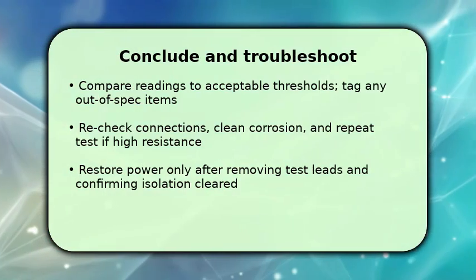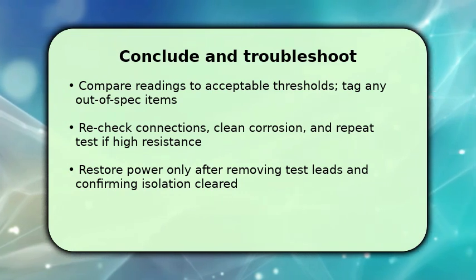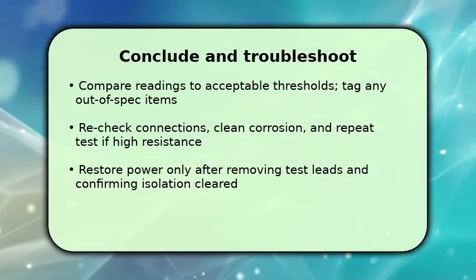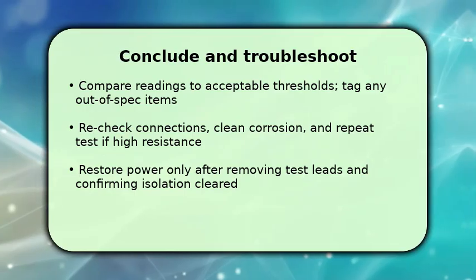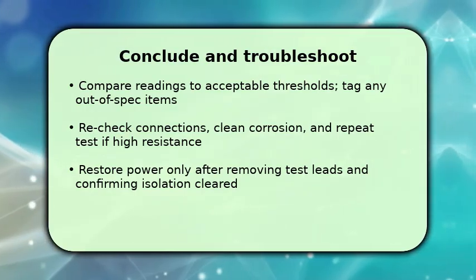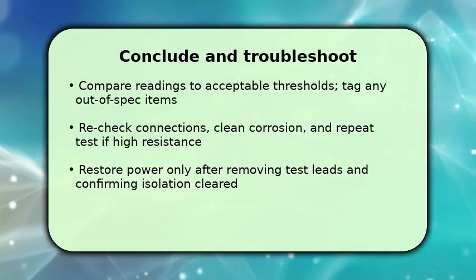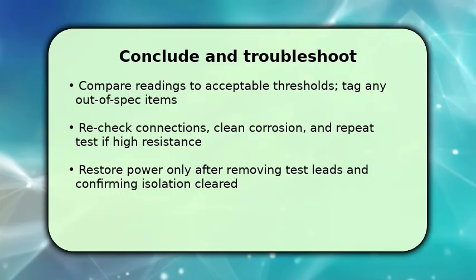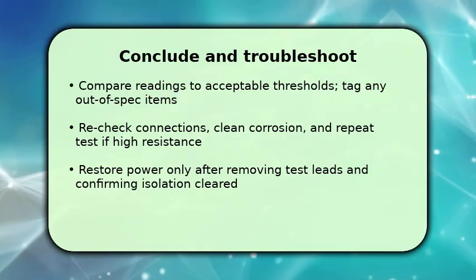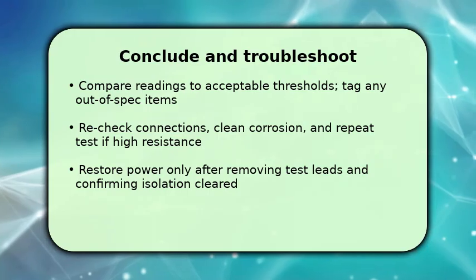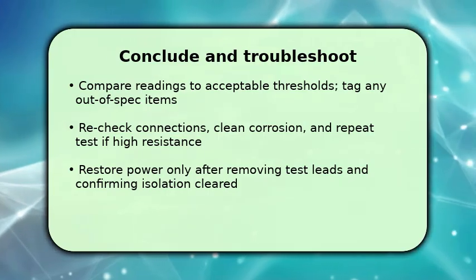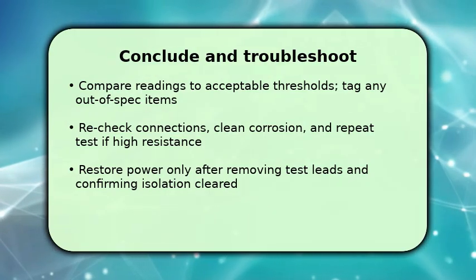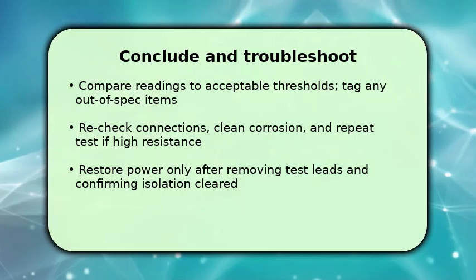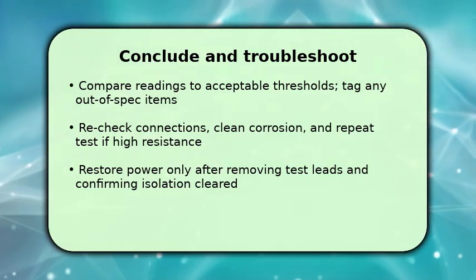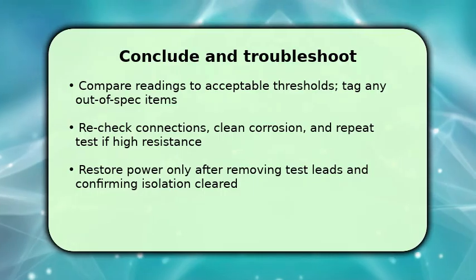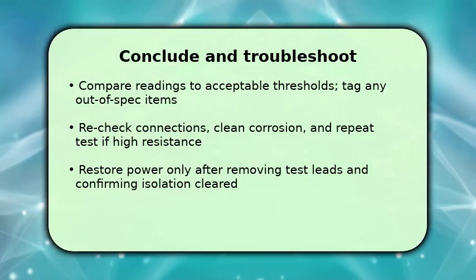You finish by comparing measured values to acceptable thresholds and tagging components that fail. This tells you what to repair. If resistance is high, recheck clamps and probe contacts, clean corrosion, moisten soil, and repeat the measurement to rule out contact issues. Make sure to remove all test leads and confirm the area is safe before restoring power. One key troubleshooting tip: if readings jump, swap probes and leads to isolate a faulty cable or a poor probe contact.